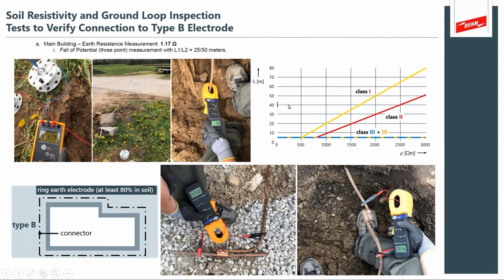So earthing, we had a couple of really nice images of what that extensive grid looks like. So the soil resistivity gives you an indication of how you can apply your earthing system. So when we did our risk analysis for that structure, we can determine if it's a high risk, then we'll need a more stringent class of protection. If you have a more stringent class of protection, you have more detailed analysis of your earthing system. So the higher, the more control of risk, for instance, at an explosive environment, you'll need a higher class, the class 1, which would then tell you on a chart like this that you'll need more earthing measures.